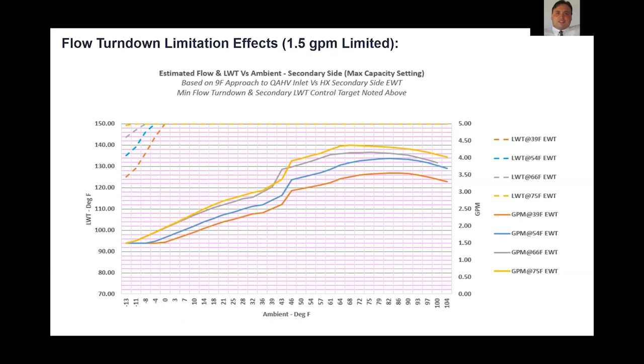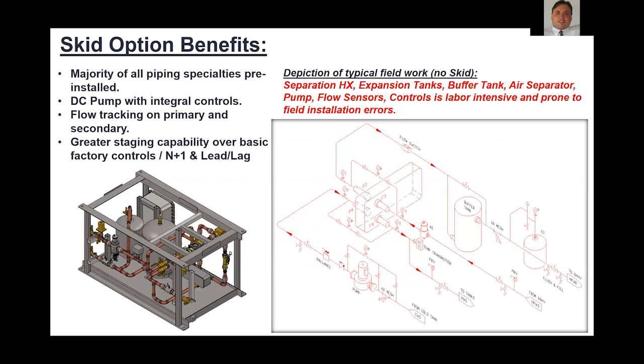These solutions really need to be considered with the manufacturer, not put on the designer or the installer to accomplish all of this, because it takes a pretty significant degree of forethought to make this all work together correctly and effectively. There are ways to simplify this, and you'll see that this is becoming more common, I think, with some of the major manufacturers in the domestic water heat pump world. You start looking at all these components that are required. Again, where it really gets complicated is on this primary to secondary side and all the controls and piping specialties that go with this. We'll get into some of that in more detail in a minute.